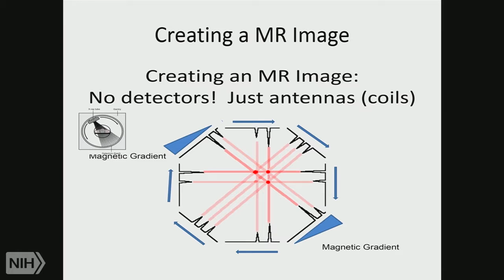One of the tricks is to apply what's known as magnetic gradients across the body in sequence. When you do that, you change the magnetic field at each point in the body, which means you change the resonance frequency at each point. So when you excite with one resonance frequency, you're only exciting a certain part of the body, not everything. The trick is to apply these magnetic gradients, increasing in strength as you go through, and you'll scan different parts of the body just by doing that. You'll steer what you're able to image just by applying a magnetic field to the patient.